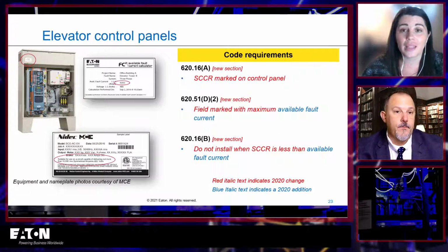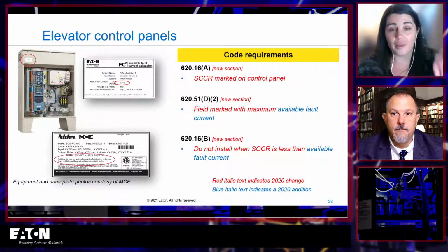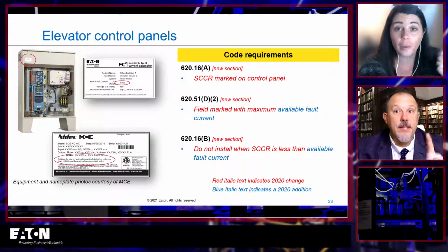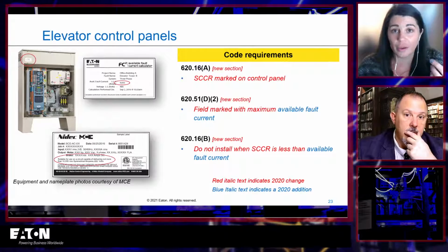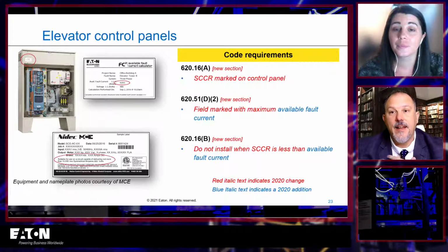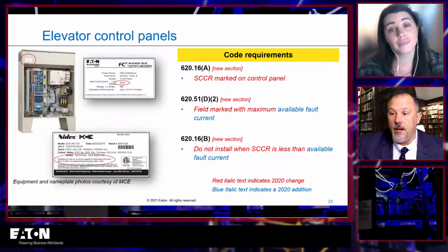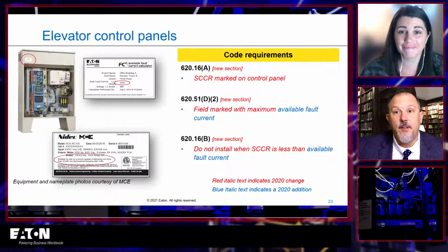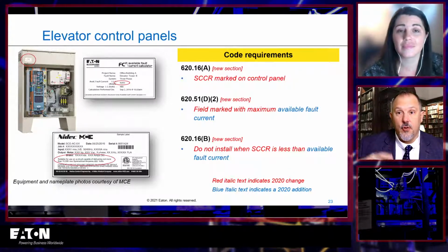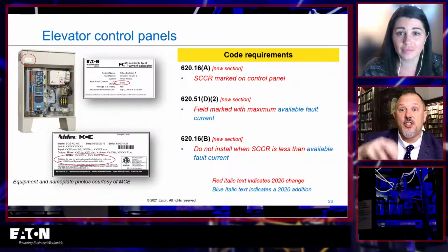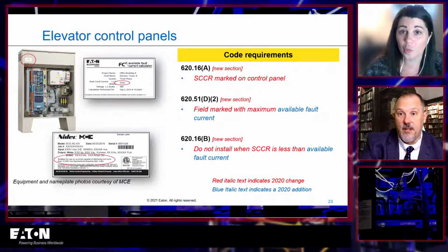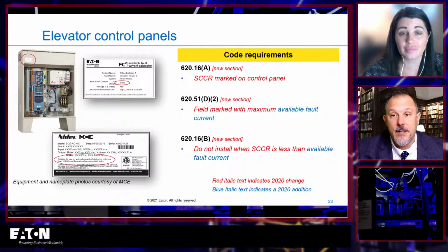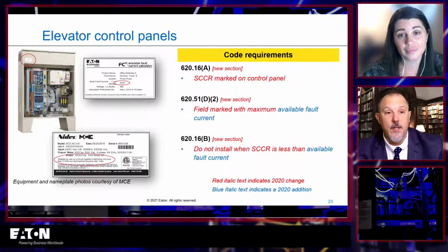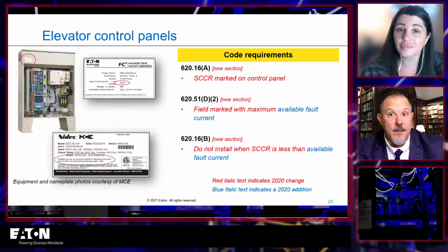Yes, I will. Elevator control panels, same. I mean, this is just repetitive here, but field marked with the available fault current, don't install where it's less than the available. The issue is that I get more phone calls on this one because the elevator manufacturers don't make anything greater than 10K. And I know there's one manufacturer of elevator control panels that basically says, you need to install this transformer in front of this equipment to knock the fault currents down. And that's a lot, I mean, you need space, you need more overcurrent protective devices. I just wish that they would raise the SCCR because it can be very simple to do.